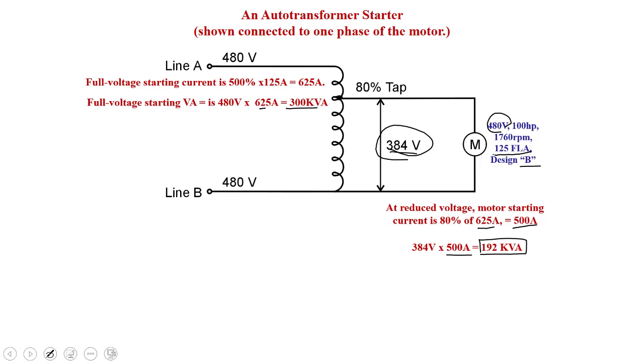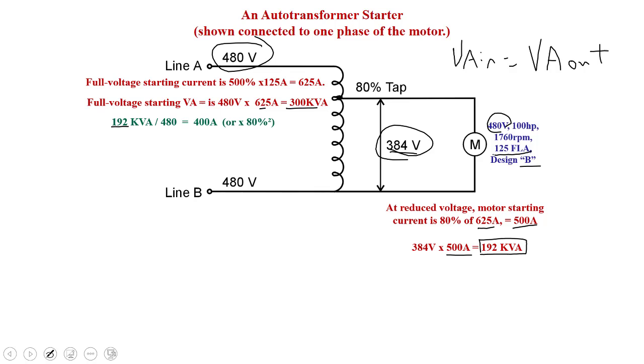Now we're only using 192 kVA at the motor. What was that first rule you learned about transformers? It applies to any transformer: the volt amp input is equal to the volt amp output. So if it's 192 kVA output, we know we've got 192 kVA input. What would be our line current? Well, 192 kVA, the line current on the primary of the transformer, divided by the primary voltage of 480, knocks us down to 400 amps. So we went from what would normally take 625 amps down to 400 amps.